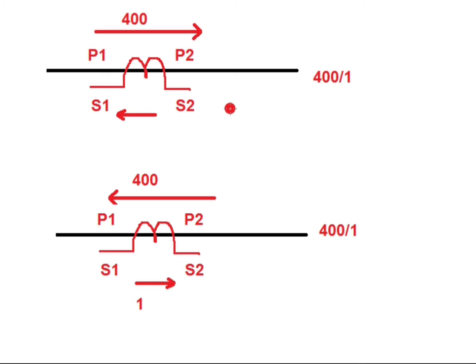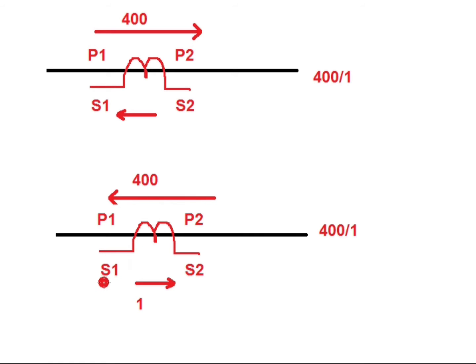How does the relay understand whether current is flowing towards the bus or from the bus? For the CT: if in the primary side current flows from P1 to P2 direction, then in the CT secondary side current will flow from S2 to S1 direction. For example, if the CT ratio is 400/1 and 400 amperes flows from P1 to P2 in the primary, then in the secondary side current flows from S2 to S1. Similarly, if primary current flows from P2 to P1, the secondary current direction will be from S1 to S2.